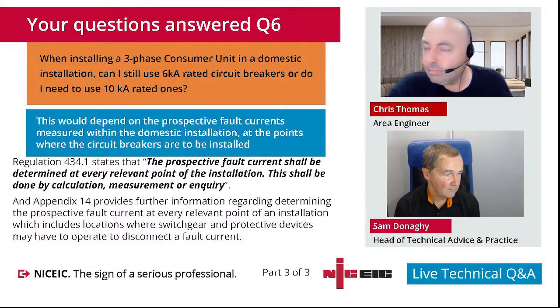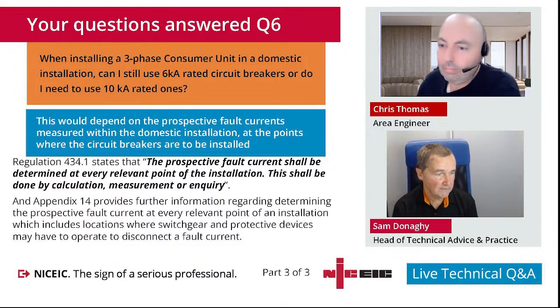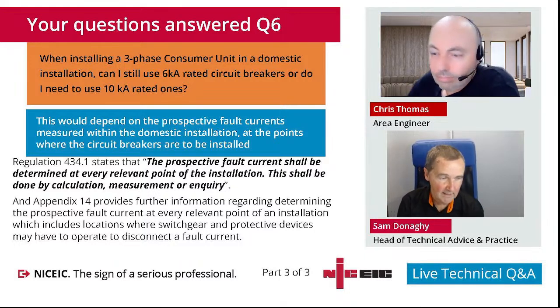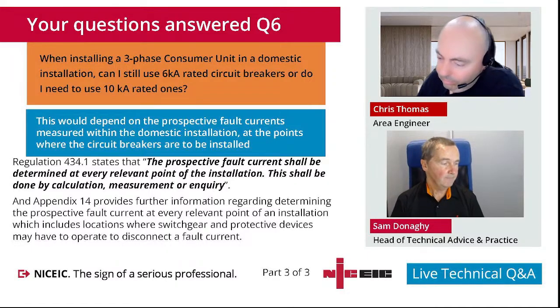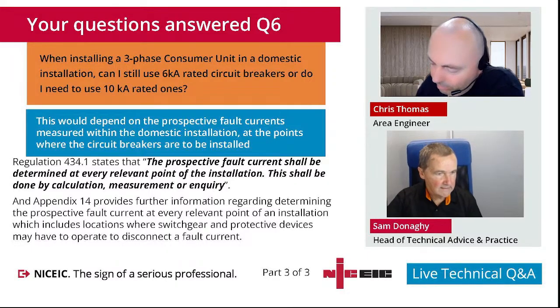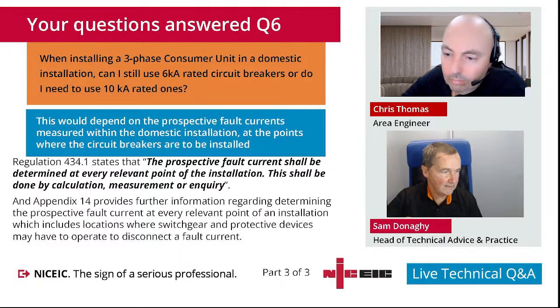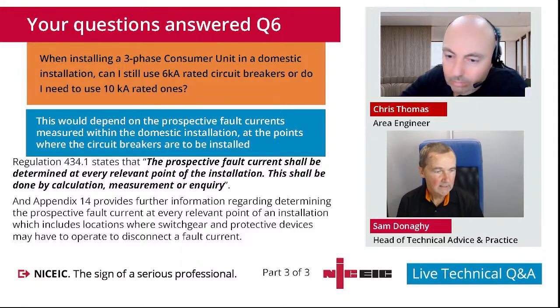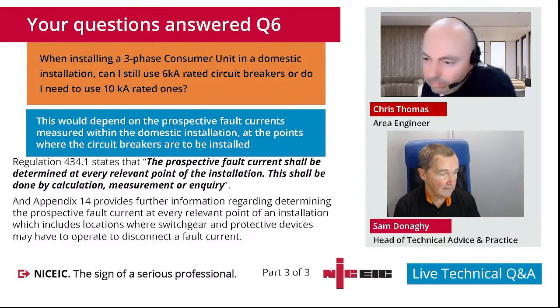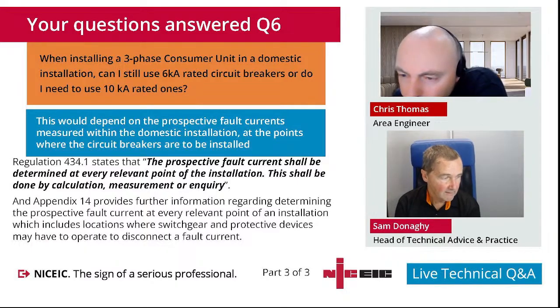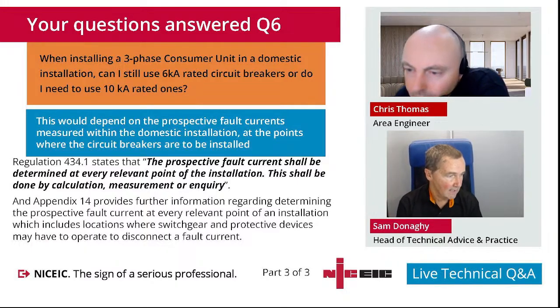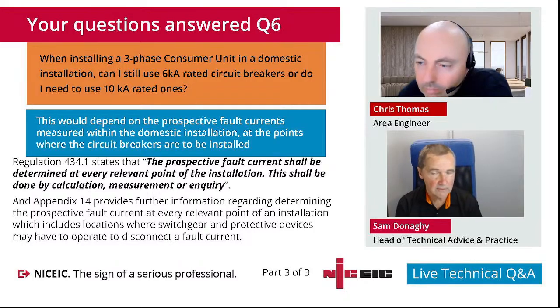There's no SPD with a new consumer unit replacement due to location restrictions. The customer was informed and accepted it. Do we mention it as a deviation on the EIC? Well, this is the engineer that asked, so could we have a look back at their answer. Thank you for repeating, if that is the repeat of the same question. Ultimately, if you stated the customer accepted that there's no SPD installed, then that meets a requirement of 7671.